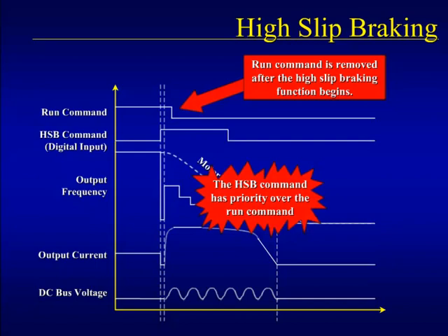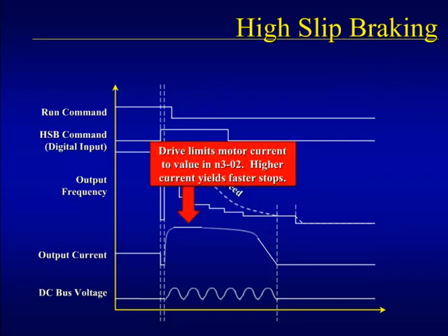If the run command is not removed, it must be recycled for the drive to run after the high slip braking function has stopped the motor. The current seen by the motor is limited by parameter N302.